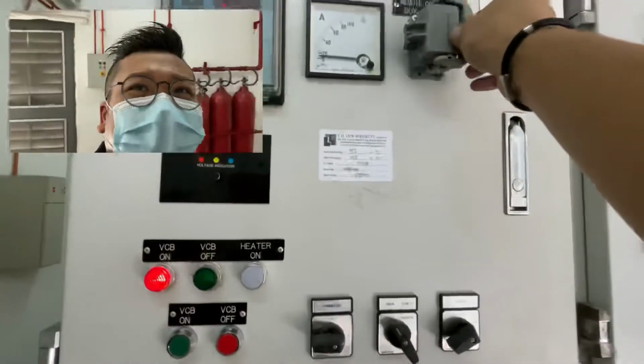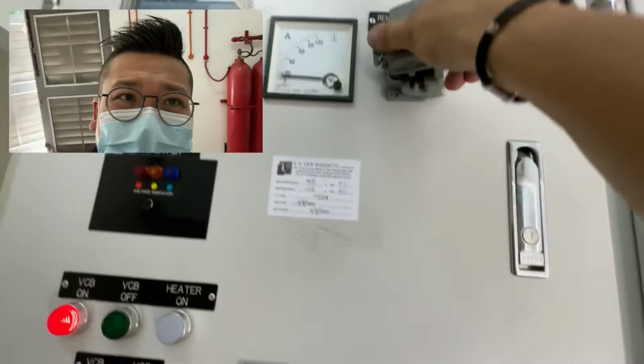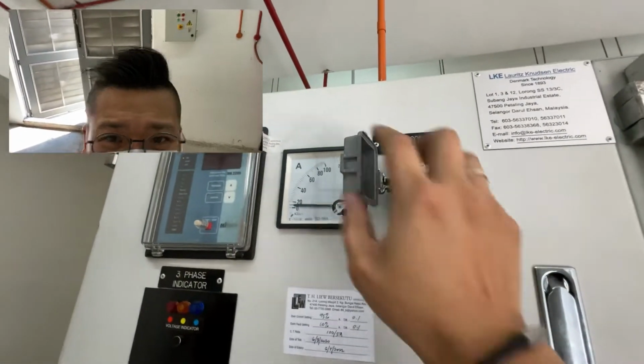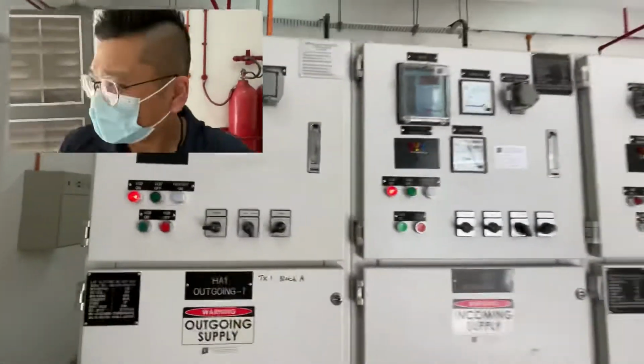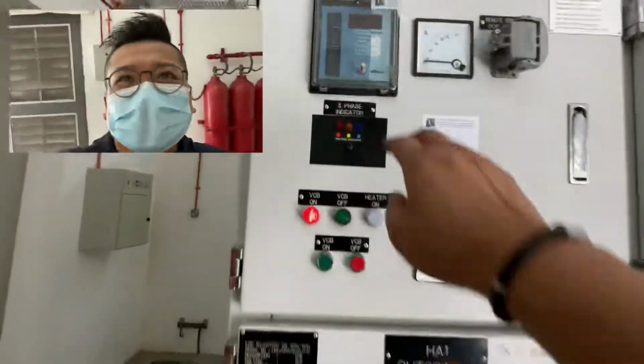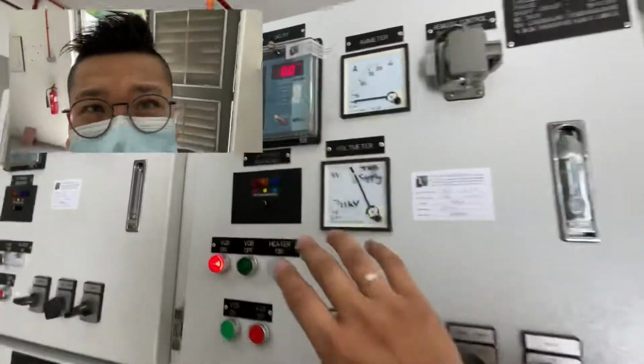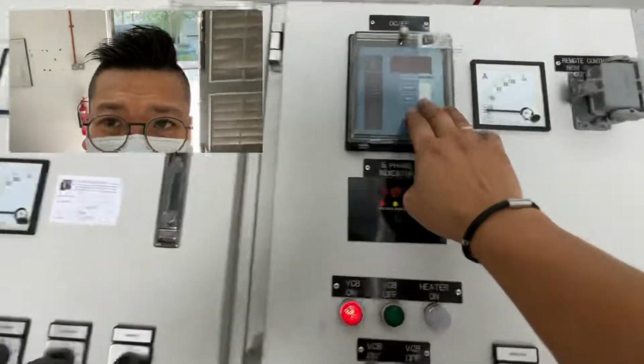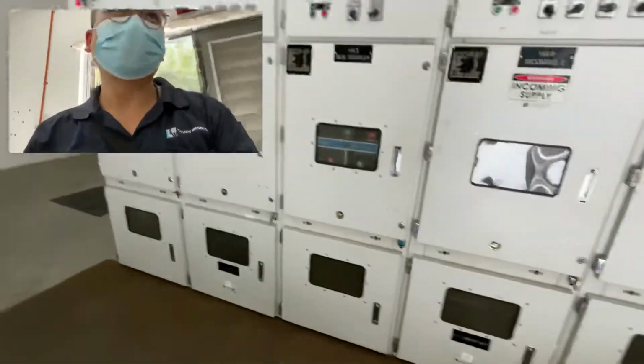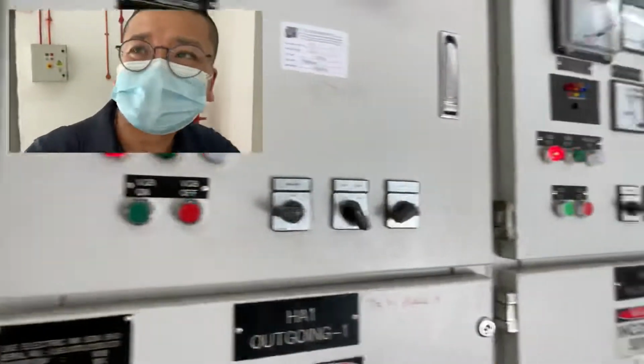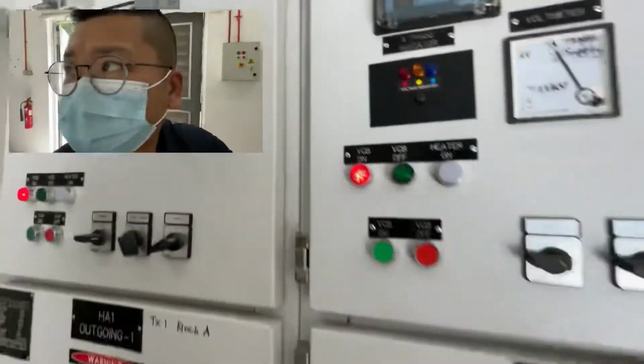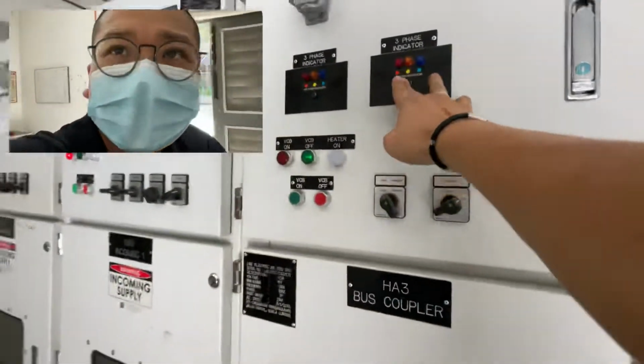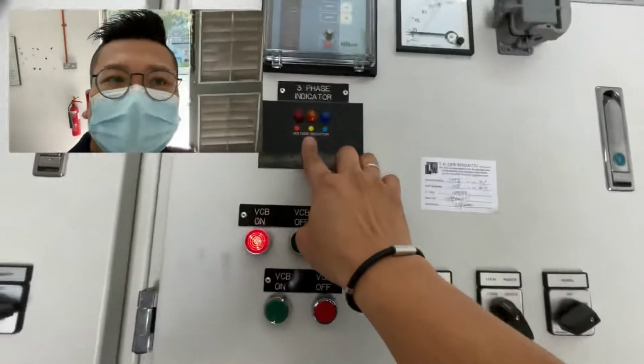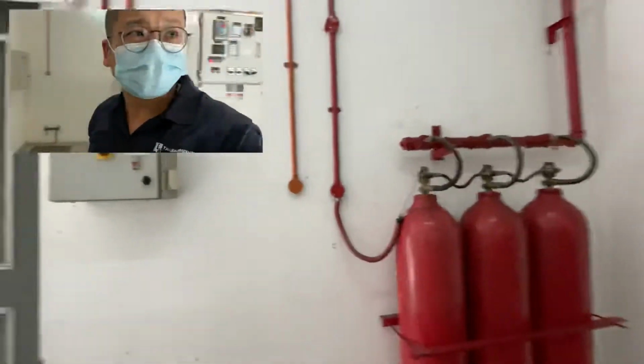This is the remote control box for the termination, where you can terminate remote switching with a cable, and then you can operate this switchgear from outside of this room. So as usual, we just check the protection relay, is it functioning properly. Indicator light. This is the coupler. CO2 system. Fire curtain, rubber mat. Rack in, rack out tools, fire extinguisher.